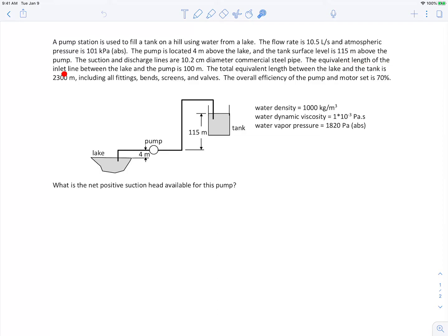The equivalent length of the inlet line between the lake and the pump is 100 meters. The total equivalent length between the lake and the tank is 2,300 meters, including all fittings, bends, screens, and valves. The idea of equivalent length is that you have the pipe length generating a major loss, and all the fittings, bends, screens, and valves cause additional minor losses.